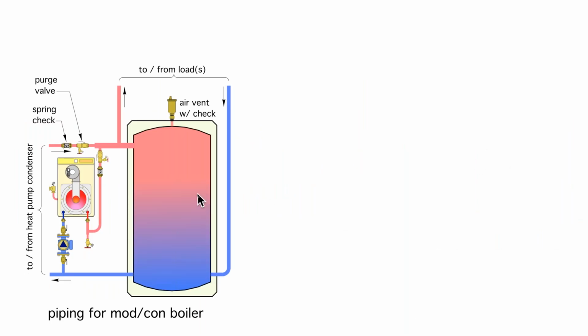This shows, again, a parallel connection where we've got a heat pump over here. And again, it could be an air to water, it could be a geothermal water to water. We've got a check valve in here, so we don't want flow, both reverse thermosiphon. We want to eliminate that, as we talked about earlier. We also don't want flow that, let's say, this circulator is creating through the boiler. We want all that to go this way. We don't want it to go back through the heat pump. So we're putting a check valve in here and a purge valve. Same thing down here. So in general, anytime you have parallel circulators that can operate independently, we don't want flow reversal through the circulators that are off. Put a check valve in, okay?